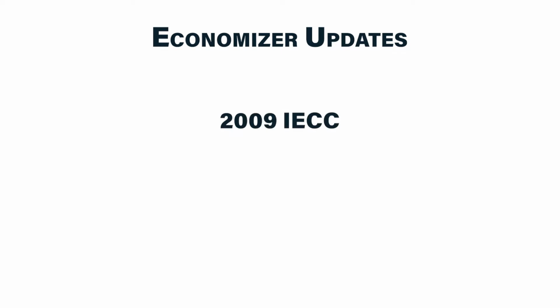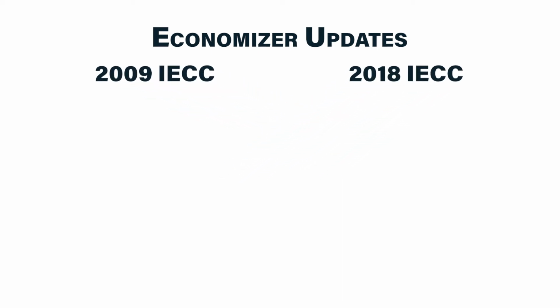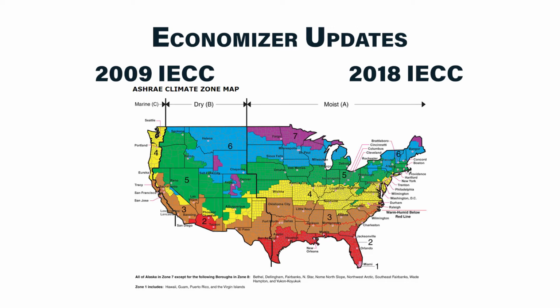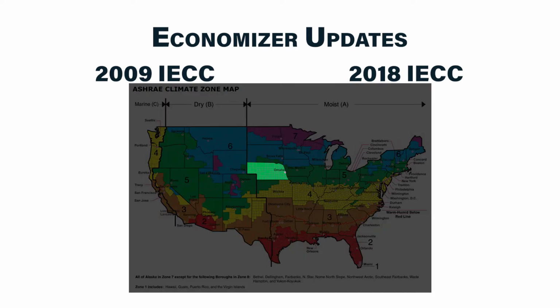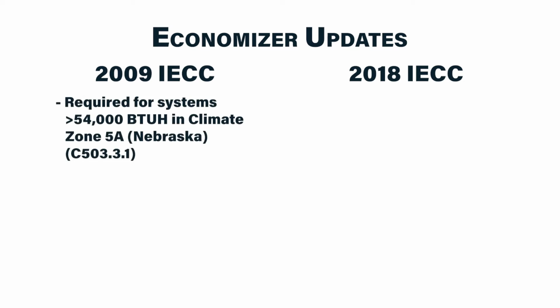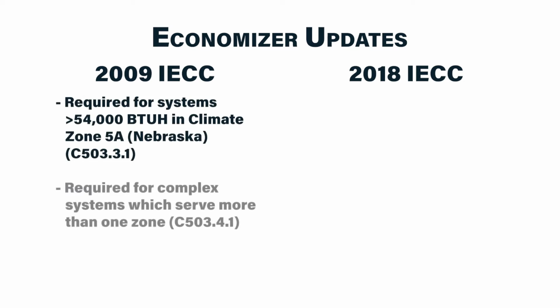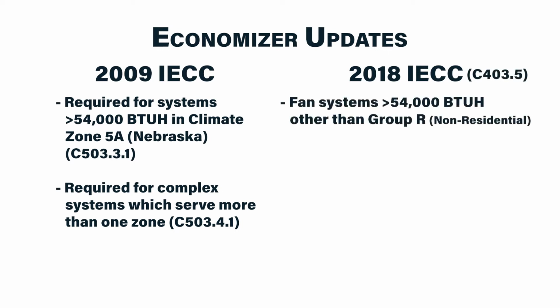In the 2009 IECC, the code outlined when to use an economizer, but didn't have a lot more details on how to use it or how to properly implement it. The 2018 IECC provides a lot more of that detail. The 2009 code required airside economizers in Climate Zone 5A, which includes all of Nebraska, on fan systems that were greater than 54,000 BTUH, which is about 4.5 tons of cooling. In 2018, that value still applies, but the code now specifies that specifically for non-residential buildings.